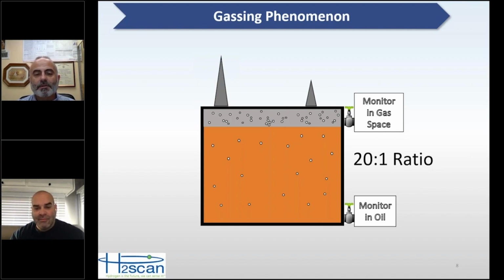And so some monitors do automatically take that into account, because there aren't really any standards that I'm aware of for giving you a good or bad value of gas in the headspace, but there's lots about DGA. So they perform that calculation and actually give you an equivalent value dissolved in the oil. Whatever the concentration is in the gas space, they'll give you that oil calculation, and so you can use the various diagnostic tools available to determine if there's something serious going on or not.